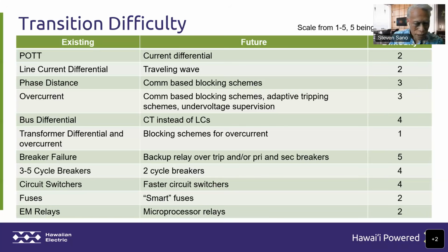Going to faster breakers, from 3 to 2 cycle breakers. Cost involved in that, space involved in that. That's at a 4. Sort of the same situation for circuit switchers. Out at a 4 to get faster circuit switchers. Fuses to smart fuses. We have been doing a bit of this work on our distribution circuits on all our systems. So that's at a 2. We kind of have a better idea of doing that. Primarily a cost issue with that.